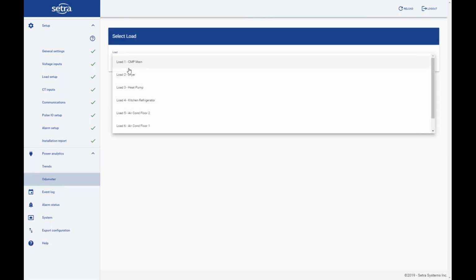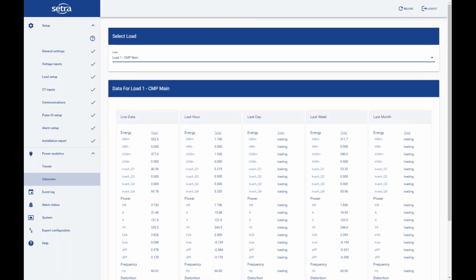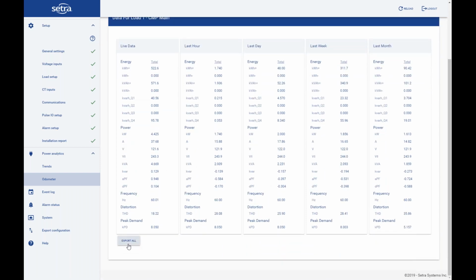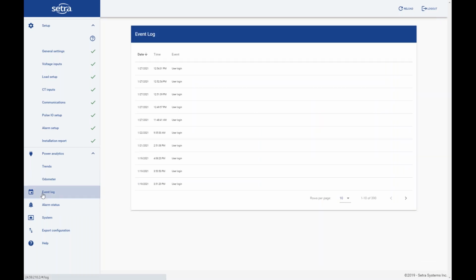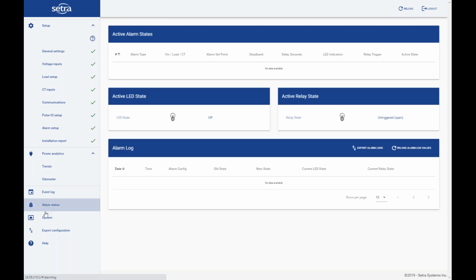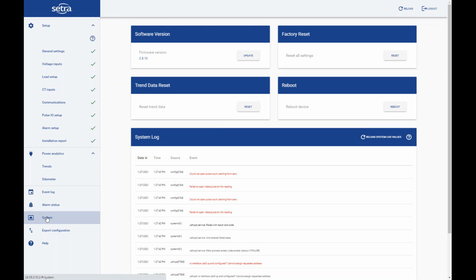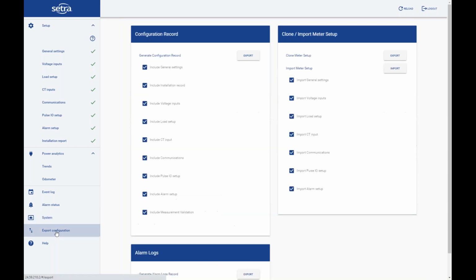In power analytics, you can see some light trend data. This is our odometer, so you can see for this load for last hour, last day, last week, last month. You can see live power data, and then you can see accumulated energy data across this. This will give you a snapshot, and you can also export that data for that load into a CSV file that you can use. You also have event logs, alarm status for anything that's set. You have a system page where you can update the firmware version, do factory resets, reset your trend data, anything like that will be on the system page.